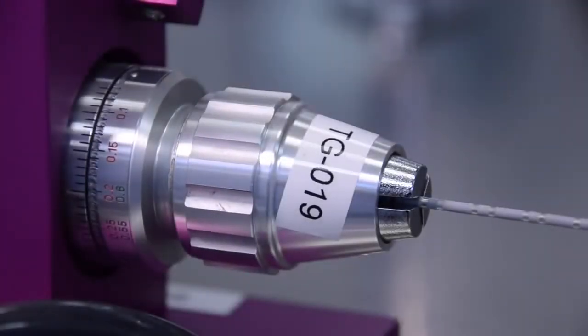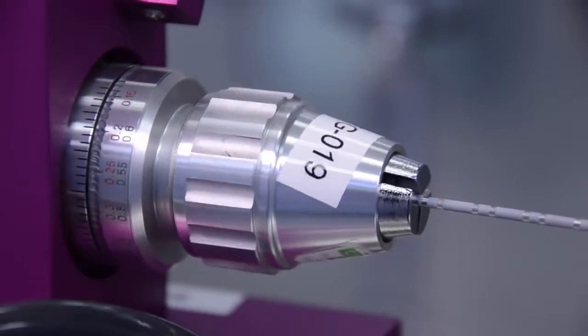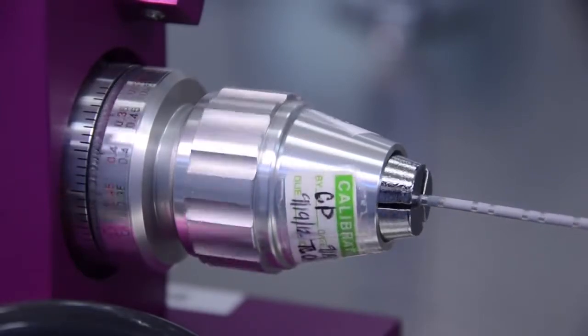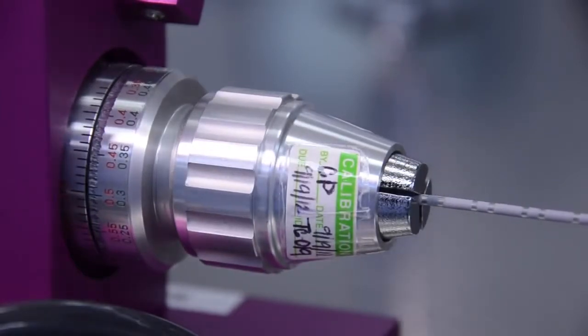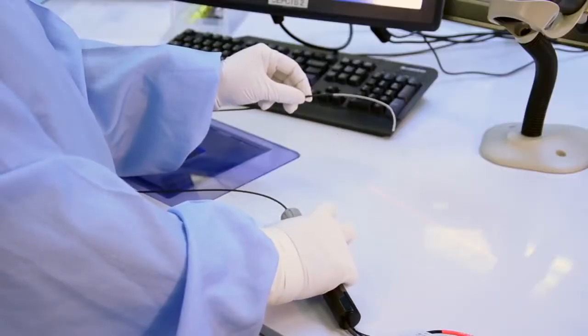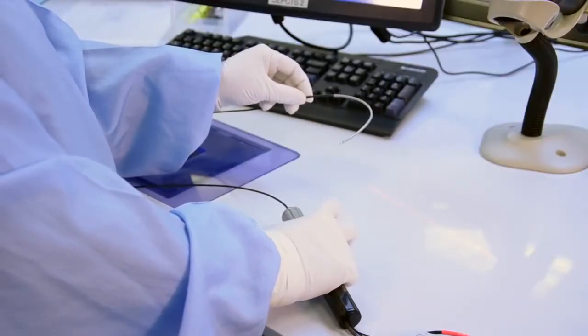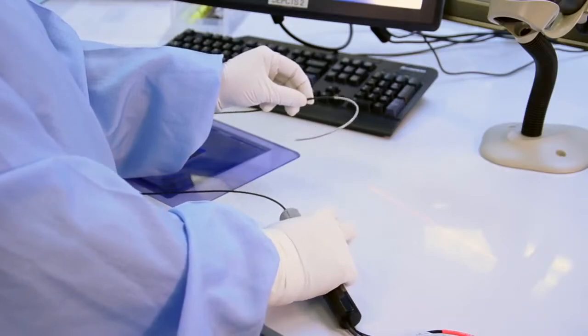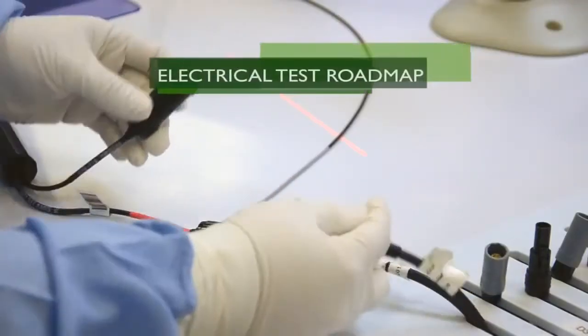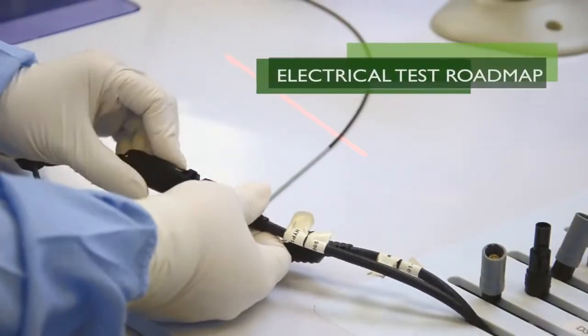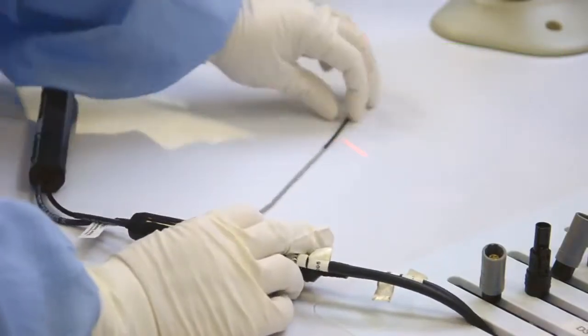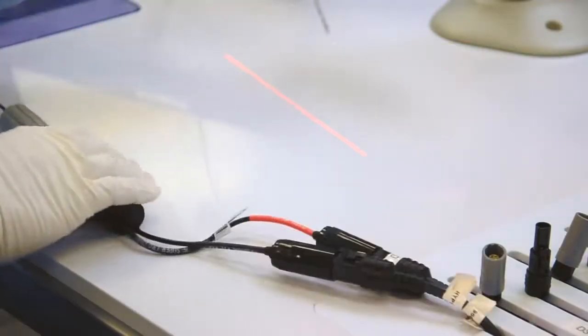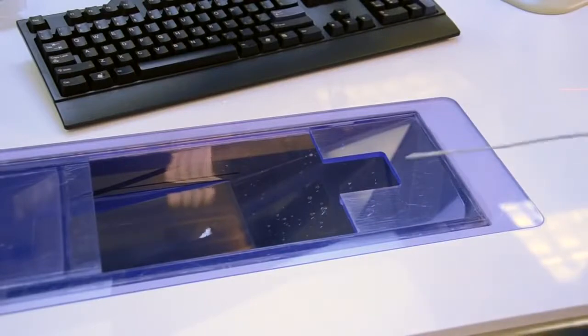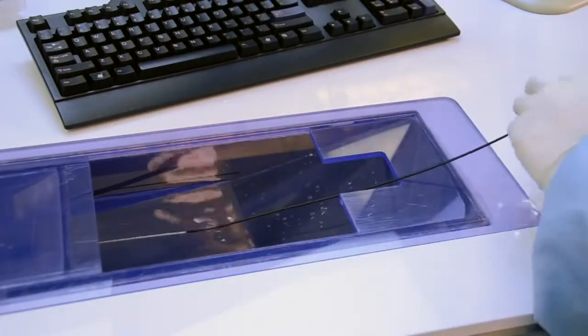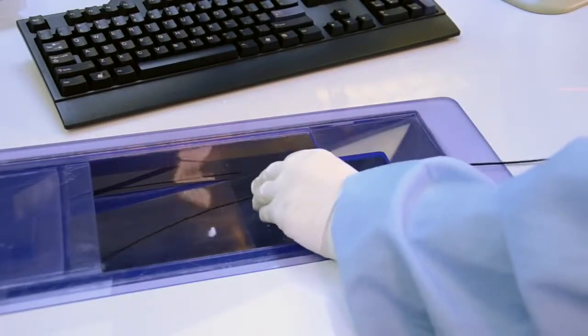Every catheter is subjected to a series of electrical and mechanical tests to assess functionality. The specifications for these tests were developed during the validation process for FDA clearance to compare their profile to that of the original device. The electrical test roadmap includes measurement and calculation of continuity and isolation using Stryker's patented electrical profile verification system. Continuity refers to the measurement of resistance of each conductive wire in the catheter.